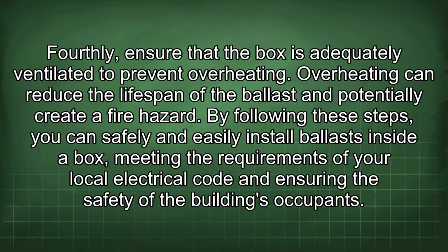Fourthly, ensure that the box is adequately ventilated to prevent overheating. Overheating can reduce the lifespan of the ballast and potentially create a fire hazard. By following these steps, you can safely and easily install ballasts inside a box, meeting the requirements of your local electrical code and ensuring the safety of the building's occupants.